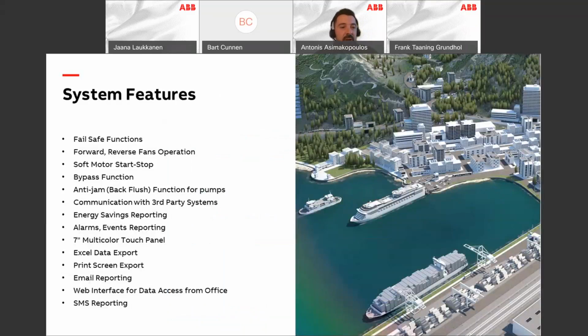Some system features: the system has fail-safe functions. It can work either forward or reverse for the fans. We can have soft motor start and stop, bypass function. For pumps, if applied, we have anti-jam or backflow operation. We can very easily communicate with third-party systems, export energy savings reporting, alarm events, the touch panel I mentioned before, email reporting, and we can also access the touch panel from the office if needed.